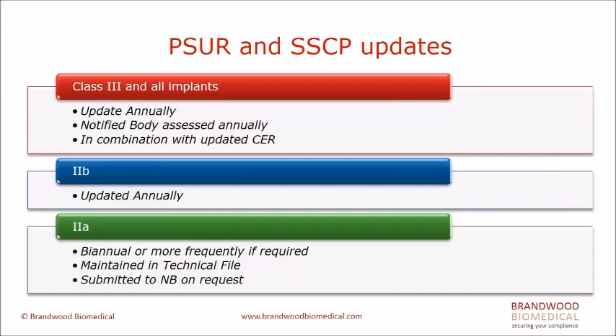For Class 2B devices as well, updated annually. Although they're not externally assessed necessarily, they'll be assessed at audit. And for 2A, every 2 years or more frequently if required, and maintained in the technical file for audit on request. So a lot of new paperwork, a lot of active requirements to review and update and document those reviews. So this is all pretty daunting.